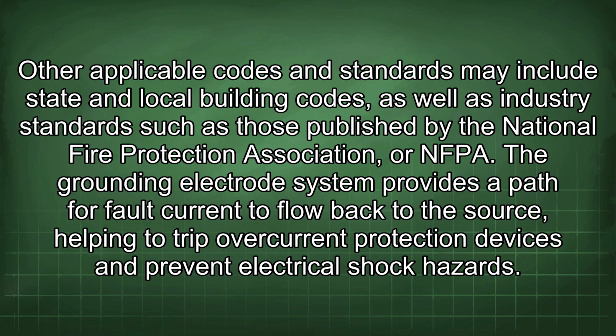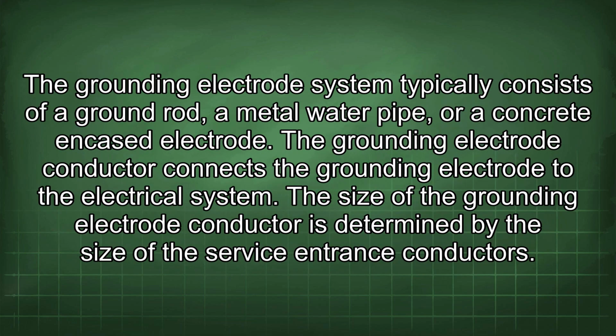The grounding electrode system provides a path for fault current to flow back to the source, helping to trip overcurrent protection devices and prevent electrical shock hazards. The grounding electrode system typically consists of a ground rod, a metal water pipe, or a concrete-encased electrode. The grounding electrode conductor connects the grounding electrode to the electrical system. The size of the grounding electrode conductor is determined by the size of the service entrance conductors.